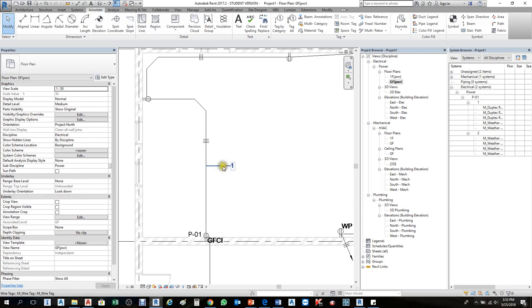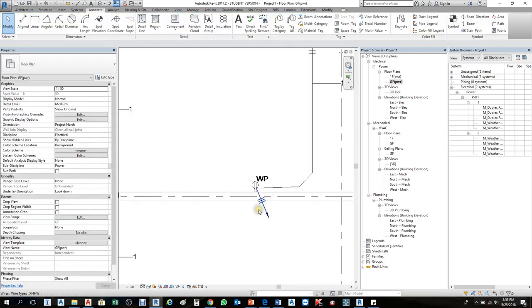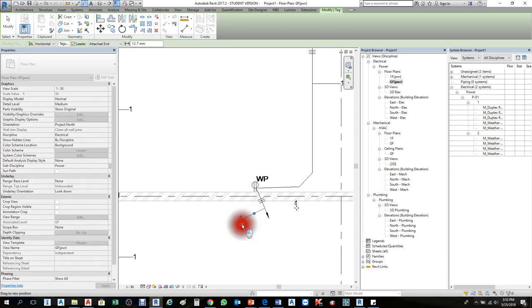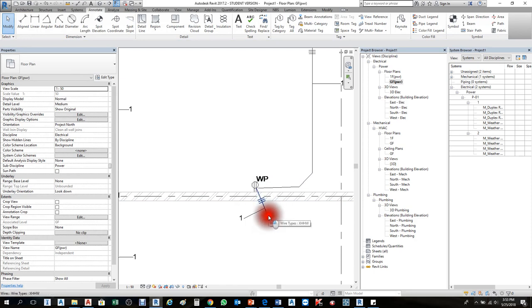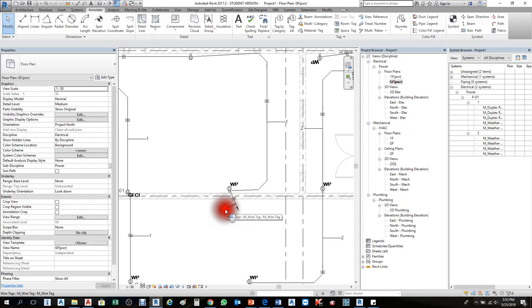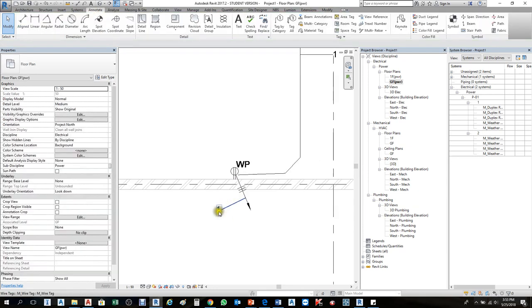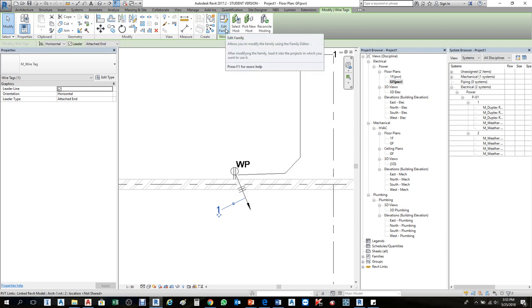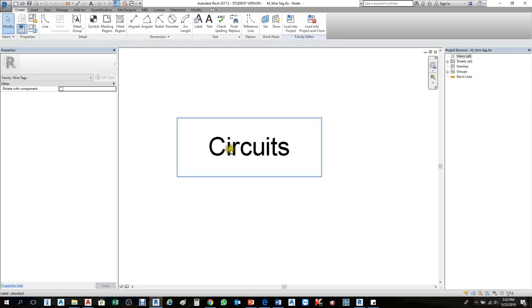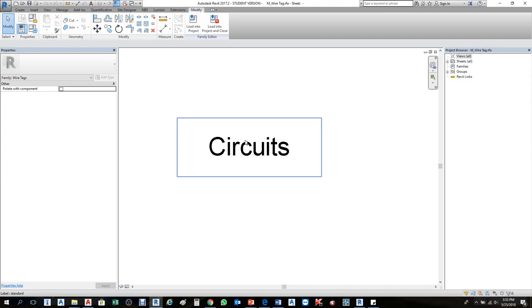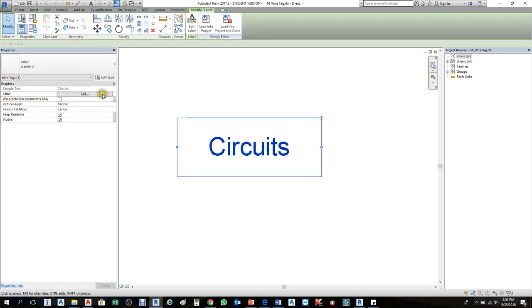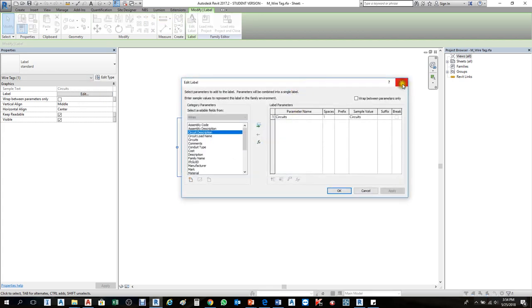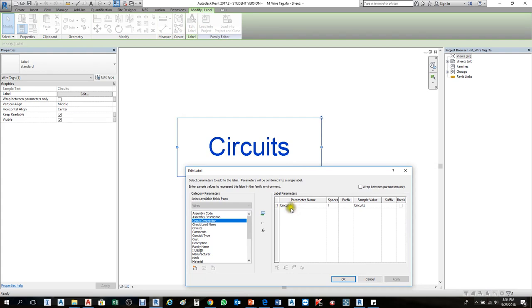If you want to change the tag — for instance, in this wire I don't want to see just the wire number, I want to see the panel number — that requires editing the label family. Select the tag, then in the ribbon choose Edit Family. In the family editor, select the label element, click Edit Label, and a dialog box appears. From the Category List Parameters, choose Panel Name and add it by pressing the green Add button. Now the tag will show both circuit number and panel name.